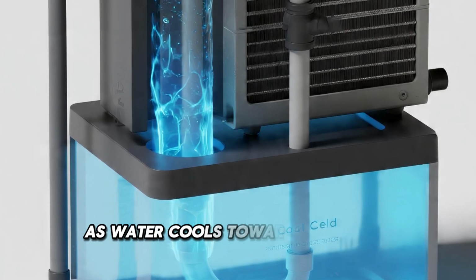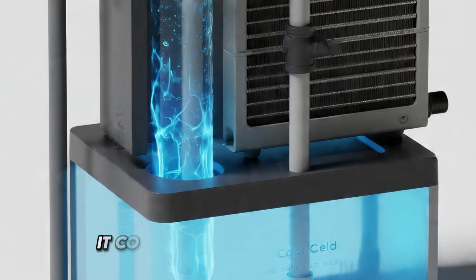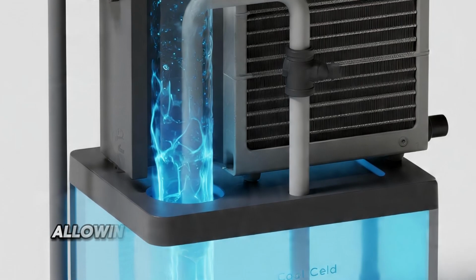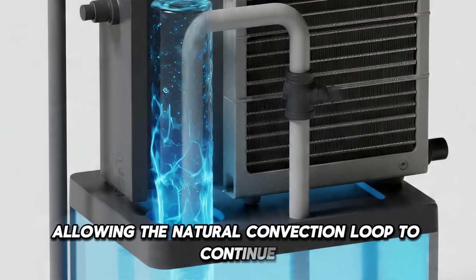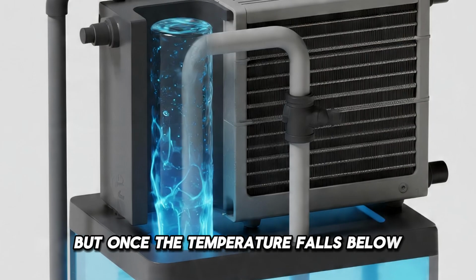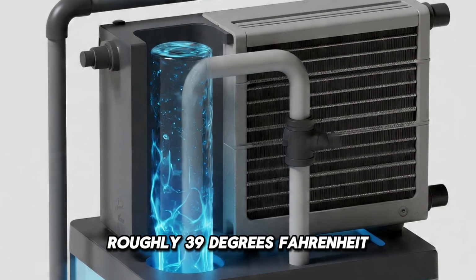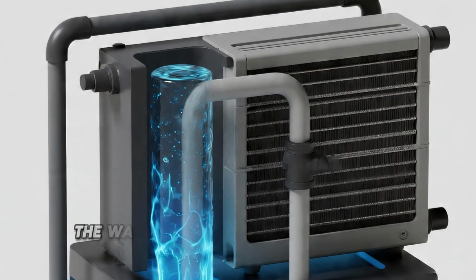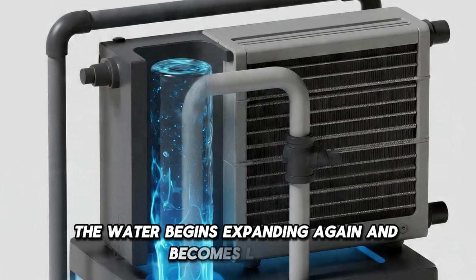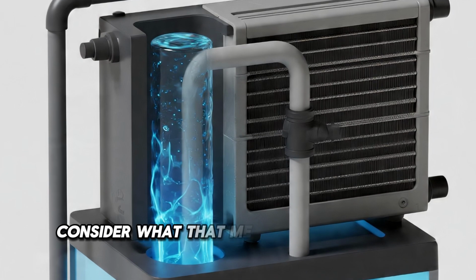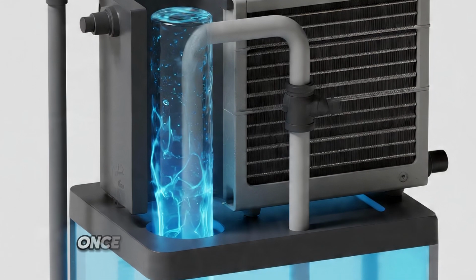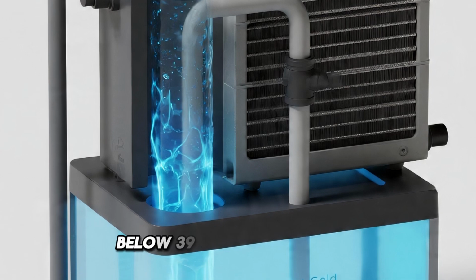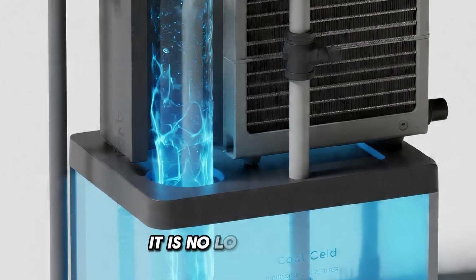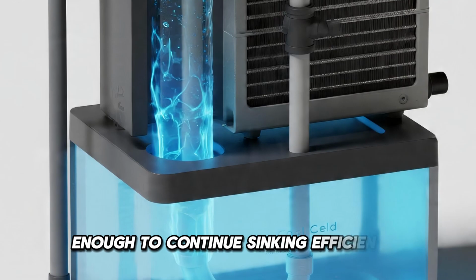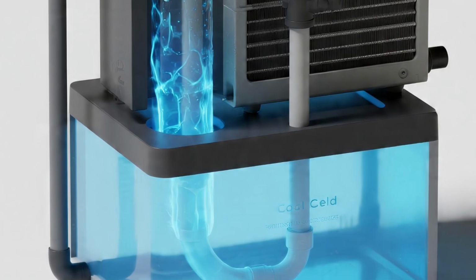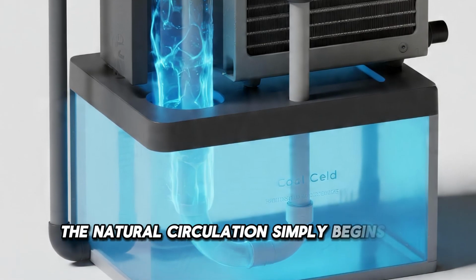As water cools toward 39 degrees Fahrenheit, it contracts and becomes denser, allowing the natural convection loop to continue. But once the temperature falls below roughly 39 degrees Fahrenheit, something strange happens. The water begins expanding again and becomes lighter. Consider what that means inside the cool cell. Once the water in the radiator drops below 39 degrees Fahrenheit, it is no longer dense enough to continue sinking efficiently toward the reservoir below. The natural circulation simply begins to stop.